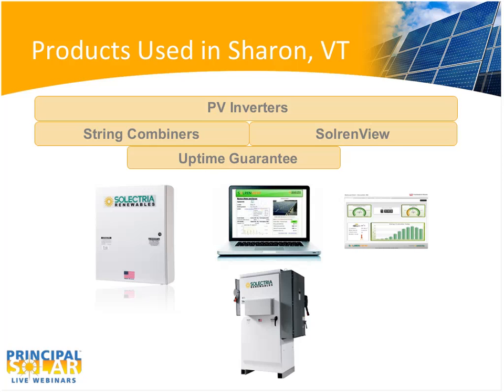As such, they wanted to put some performance guarantees on the inverter. So in this deal, we worked out what's called an uptime guarantee on the inverters, which is essentially a guarantee of a certain percentage - usually 99 or 99.5% inverter uptime - guaranteed by us, by Solectria, the inverter manufacturer, to the owner of the system. So in the event that the allowable downtime is exceeded, Solectria is actually under contract to reimburse the owner at a fixed reimbursement rate. So we have an uptime guarantee in place on this project.